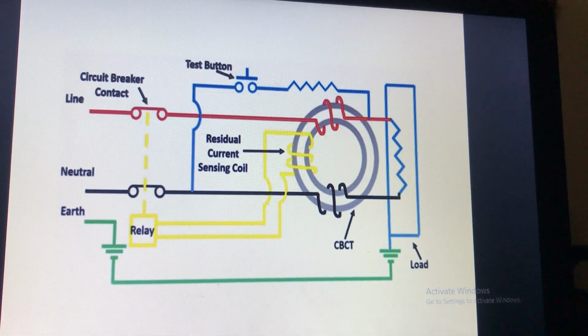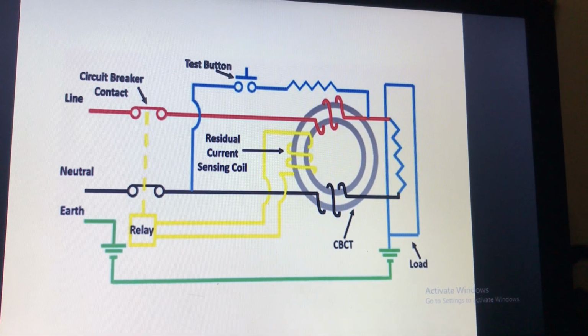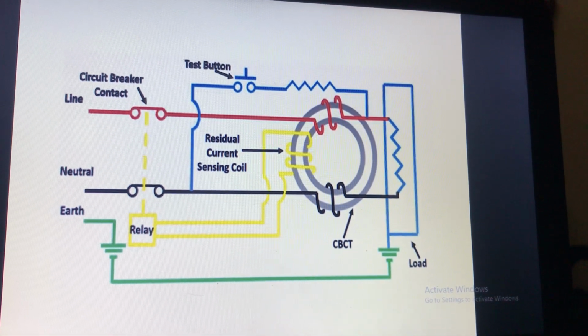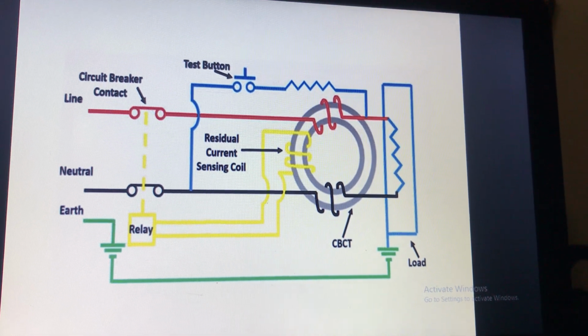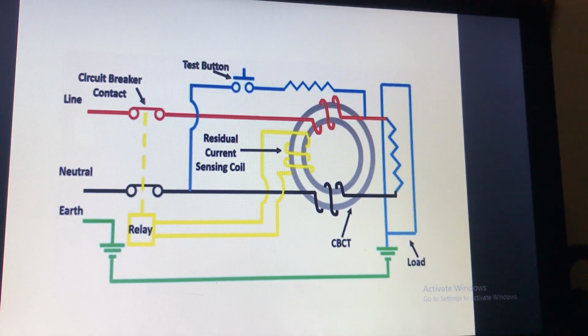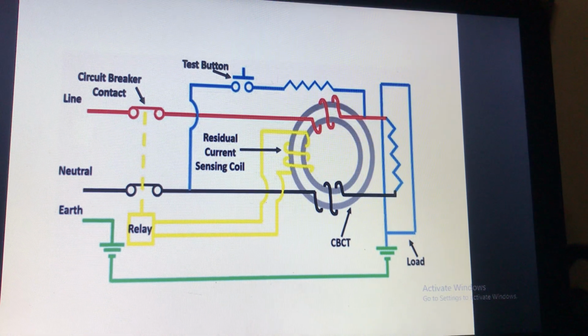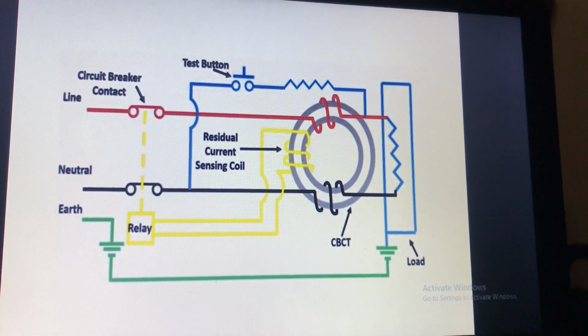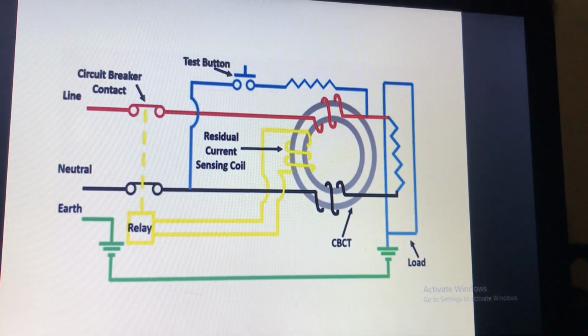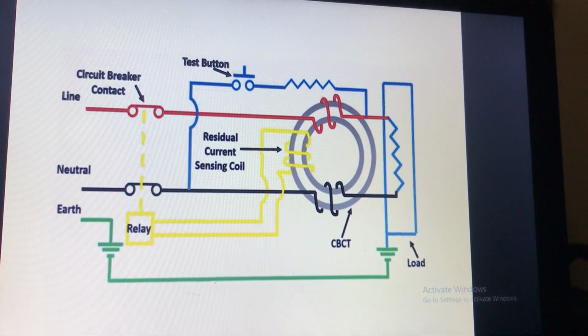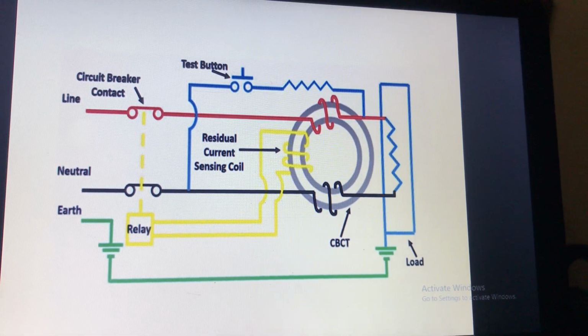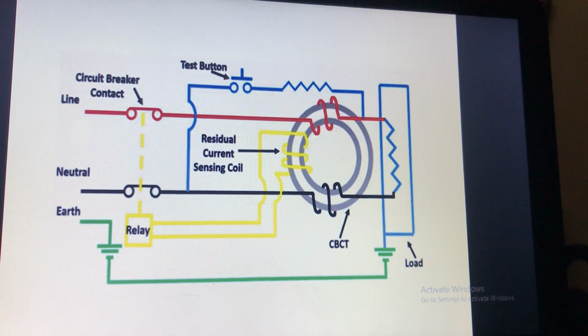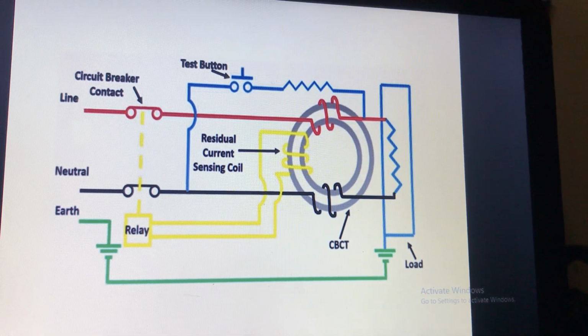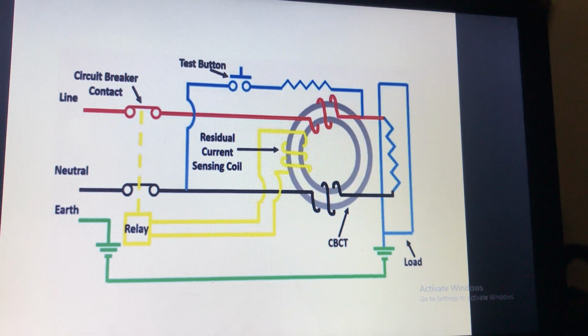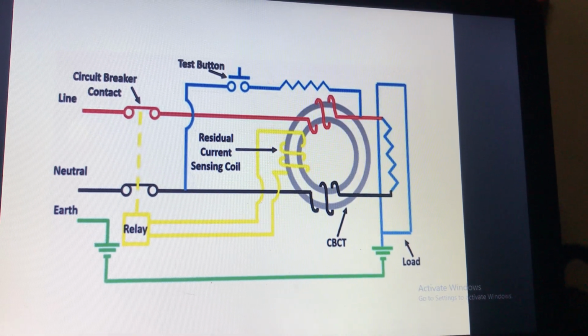And you can see there is one operating coil, the residual current sensing coil. This is the operating coil. It is also on that transformer core. So in case of imbalance of currents, this residual current sensing coil will detect that imbalance and operate the relay, because in case of imbalance there is a flux in the core and then the EMF will get induced in this coil and it will operate the relay and open its contact.